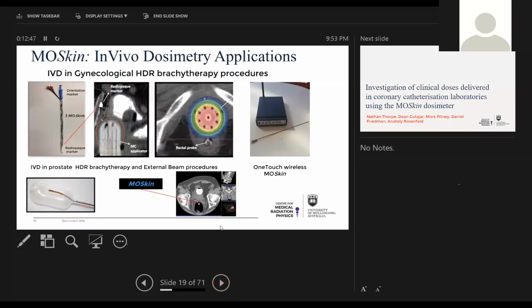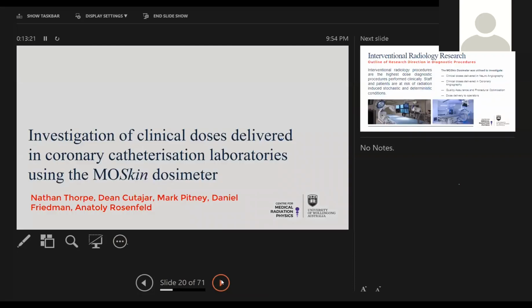So these detectors we are using in different applications, gynecological applications, in multi-way collimator to measure dose on the rectum during the treatment. We're using it in a rectum balloon for immobilization of the prostate and to get dose measurement on the anterior rectum wall. So it's very convenient, it's a disposable detector and always reproducible. It doesn't matter, out of 1,000 detectors, you have 70 micron plus or minus 5% depth of dose measurement.